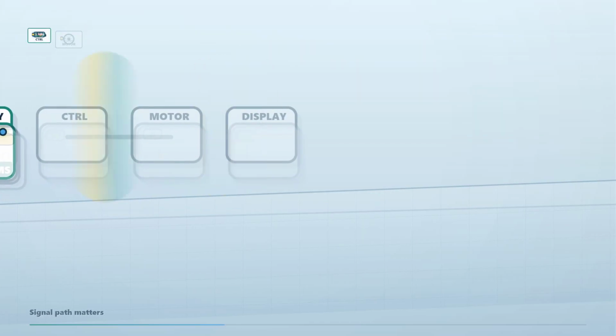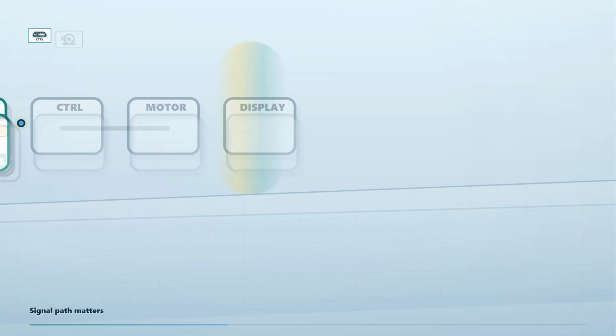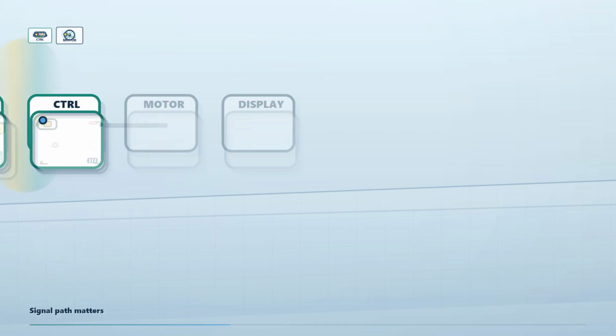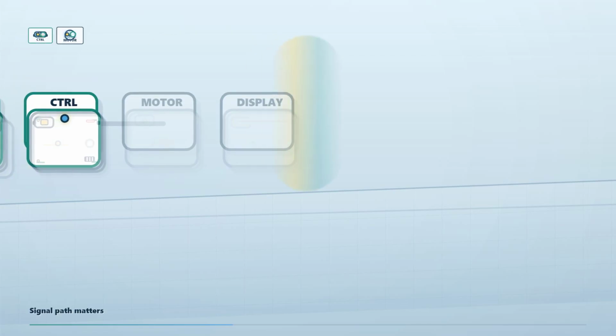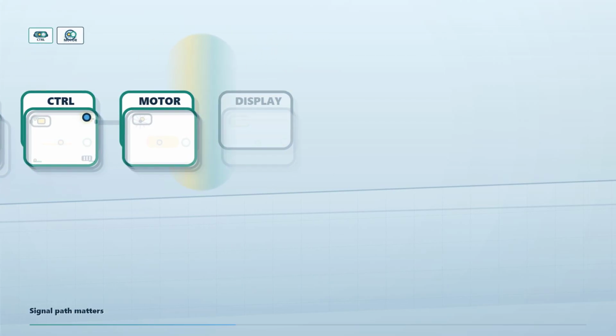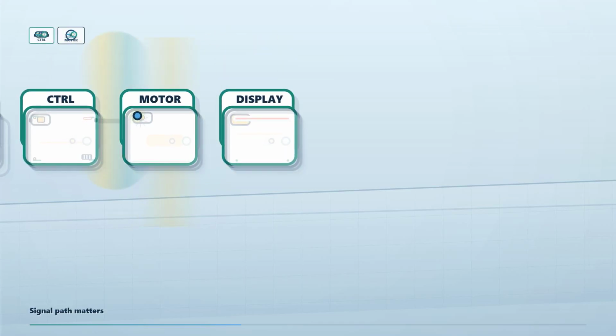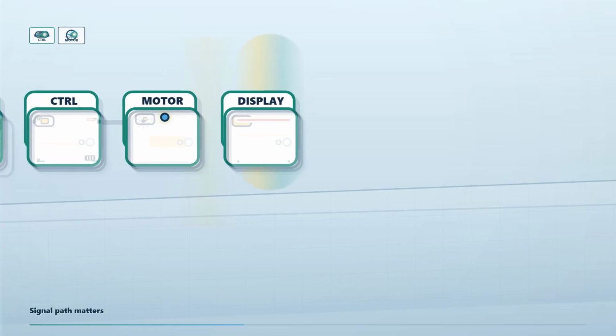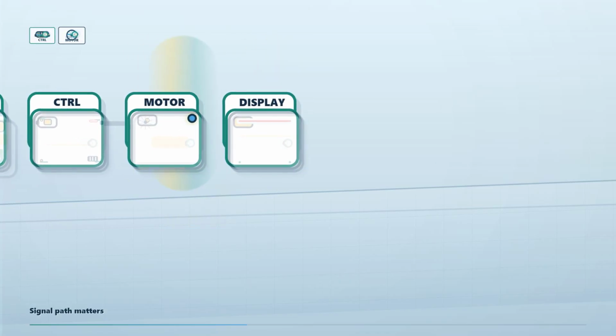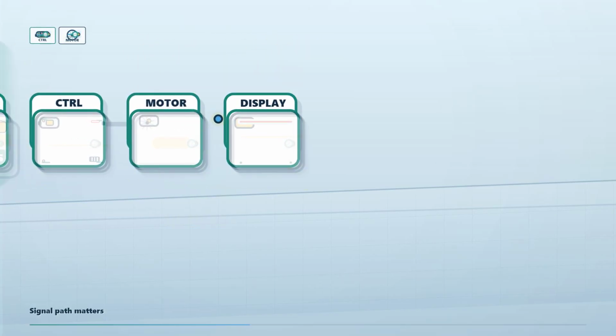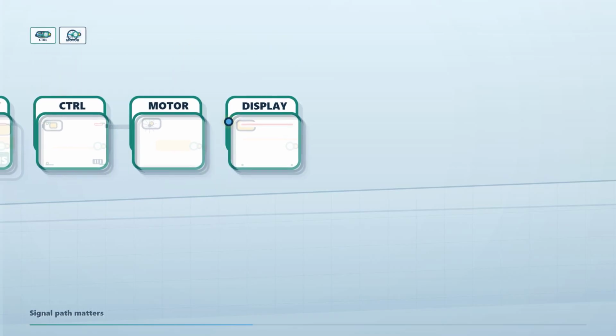The display can still help here, even though it does not prove the battery is bad by itself. If the controller and display are getting unstable power, they may flicker, shut down, or show strange behavior that points back into the power path. That clue matters because the battery problem and the control problem can overlap. So read the display as evidence, not as a final verdict. It tells you where to look next.